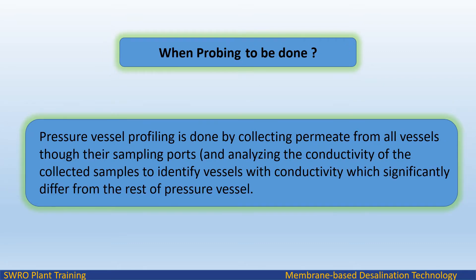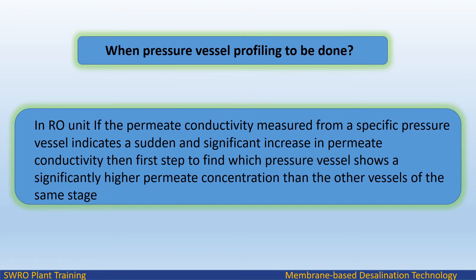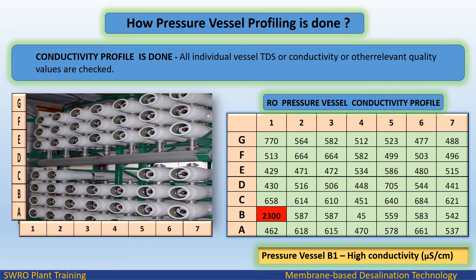When should probing and profiling be done? Pressure vessel profiling should be performed when the permeate conductivity measured from a specific pressure vessel indicates a sudden and significant increase. The first step is to find which pressure vessel shows a significantly higher permeate concentration than the other vessels of the same stage.